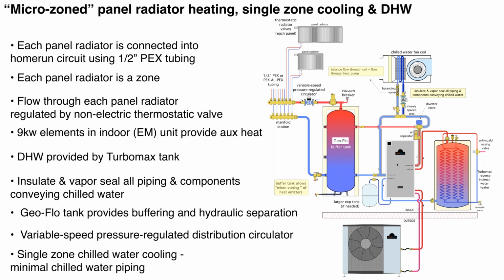What this does is it allows the circulator in the heat pump to provide flow in this loop right here, okay? Relatively low head, low pressure drop loop. And then this circulator picks up that chill water, sends it up through the coil, brings it back, drops it back into that loop. By keeping these tees close together, we're hydraulically separating the pressure dynamics of the circulator that's in the indoor unit from the circulator that we've sized specific for the chill water coil, okay?